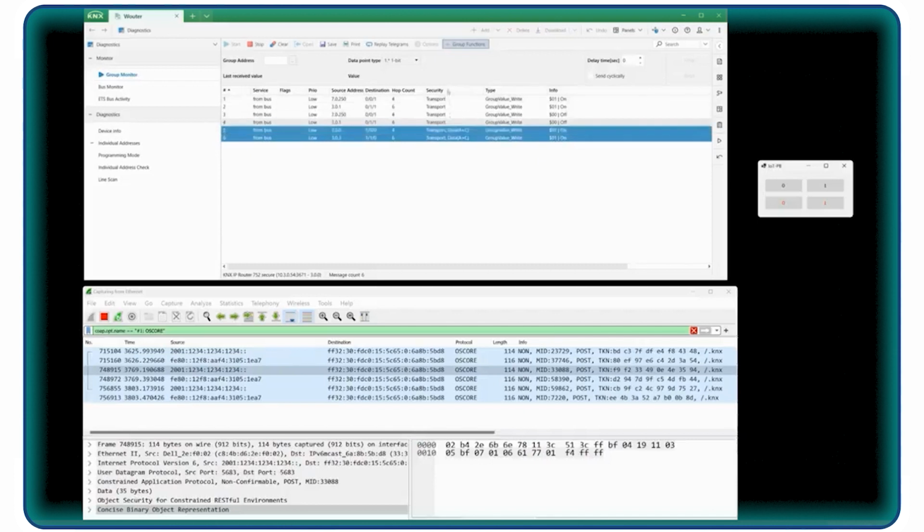It's indicated in the security tab here. So not only transport, so not only was it wrapped into an IP secure frame, but inside that wrapped IP secure frame there is indeed a frame for which data security is applied. That goes in two directions: from the push button to the actuator, and from the actuator back to the push button for feedback. That's also how we can distinguish the different group addresses. The 1.0.0 is for triggering, and 1.1.0 is for the feedback.